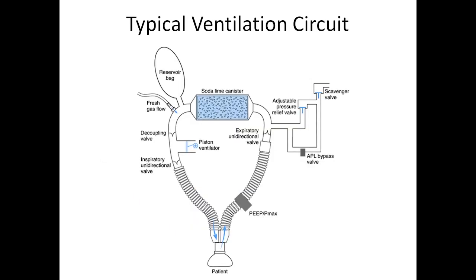So this is a typical ventilation circuit. You see over here we have an expiratory and an inspiratory, which means this is where you inhale and this is where you exhale. As you inhale, it comes over here, you get fresh gases mixed with some recirculated gases, and it squeezes it to a certain quantity, it goes into the patient, and then the patient's own elasticity will exhale, and it comes over here to another one-way valve and out the machine.